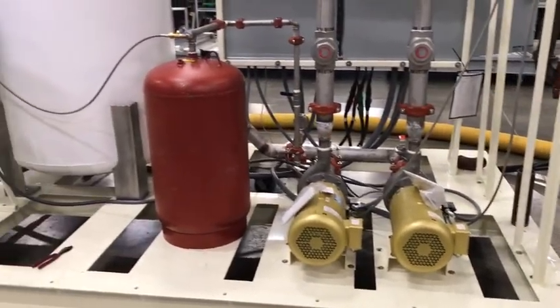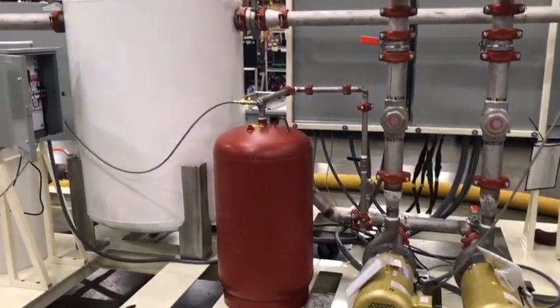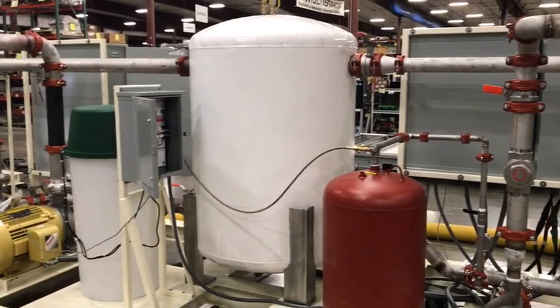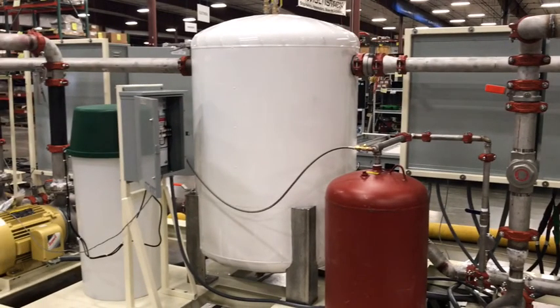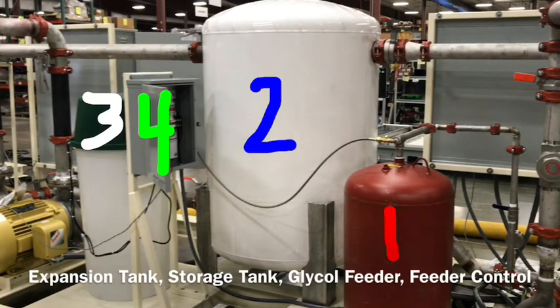First in our view there is the maroon bladder type expansion tank, the large storage tank, which also serves as a decoupler in this system. And then shown in white number 3 there is our large glycol feeder. Item 4 is the junction box that has controls and power for the glycol mini feeder. So again, three types of tanks. Number 1, expansion. Number 2, storage / decoupler. And number 3, the glycol feeder tank.